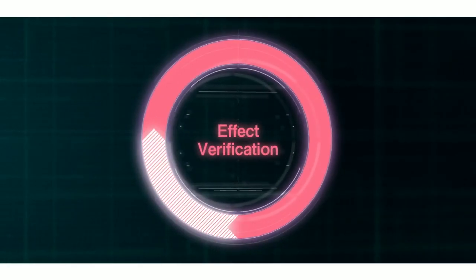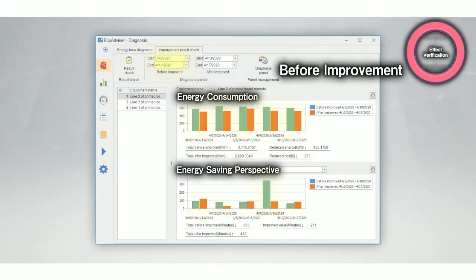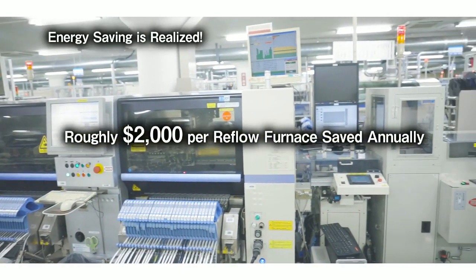The last process is effect verification of energy-saving measures. Verifying the effects of pre- and post-measures by sorting through and comparing the data was time-consuming. EcoAdviser allows us to see the effect of improvements on energy-saving, operating rate, and others numerically by simply specifying pre- and post-measure periods. In this case, roughly $2,000 was saved annually by improvements in only one reflow furnace.